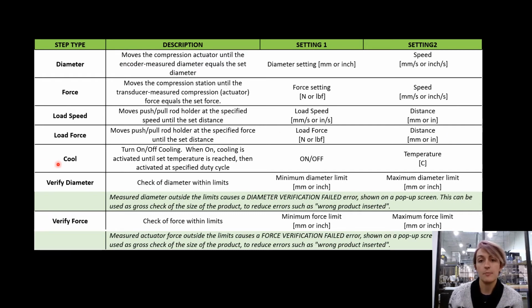Then we have the cooling step type. This step type is either an on or an off setting. When you turn the cooling on, you can also set a temperature that you want the station or the system to reach before it moves on to the next step type. It's important to remember that this setting is not a temperature controlled setting for the loading process. This temperature setting is simply telling the machine that you want it to reach this temperature before it moves on with the rest of the loading process. During the loading process, what's controlling the flow of the liquid nitrogen is the duty cycle setting that you set in the general recipe settings box.